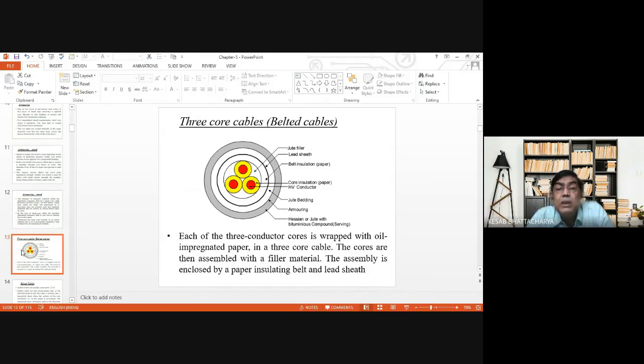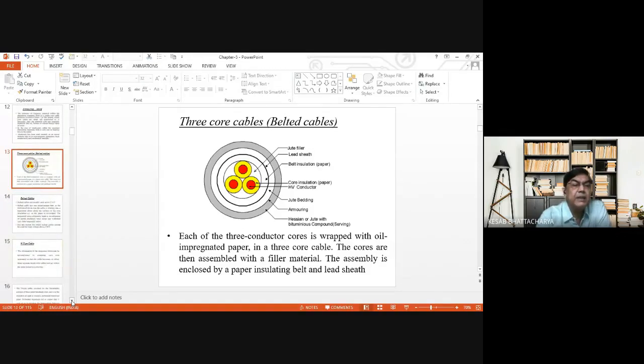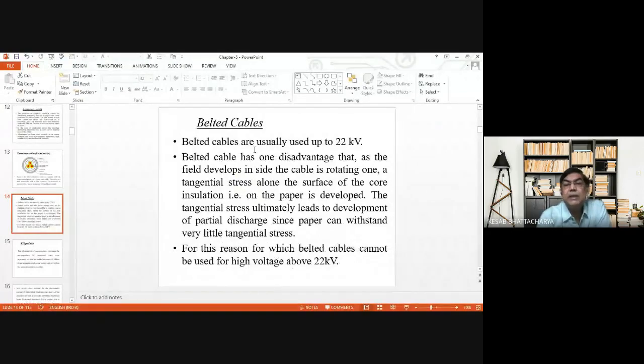So far as high voltage engineering is concerned, this type of cable, three-core belted or paper insulated cables, suffers from a limitation: these cables cannot be used beyond 22 kV. Why this is so is of our interest, and that is discussed next. The belted cables are usually used up to 22 kV.